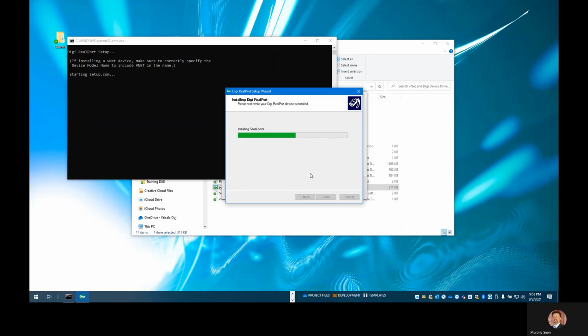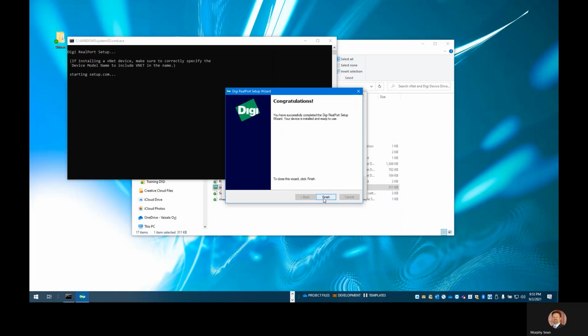You can go through this blind setup where you type in an IP address and you map a COM port to it. And then when you go to install the hardware after the fact, it just comes online immediately. So you don't necessarily have to have the hardware installed. Sometimes if you're doing a large system installation and you have a network drop that's just not functioning, you can go through this step and set up the drivers for it and then deal with the issue with that physical port later on. And the driver's already there, so it'll come right online inside of viewLinc as soon as you remedy that issue with the switch and the hardware.